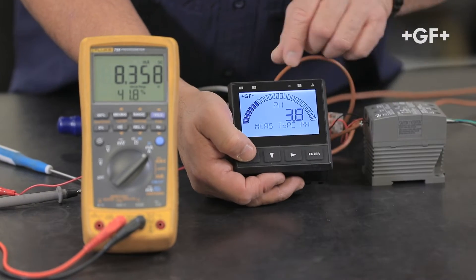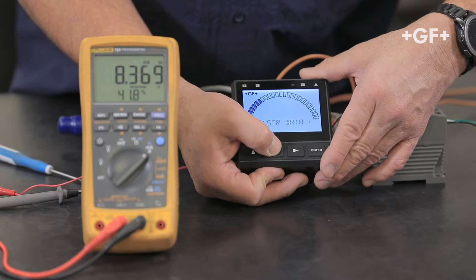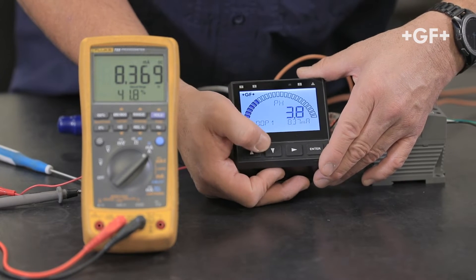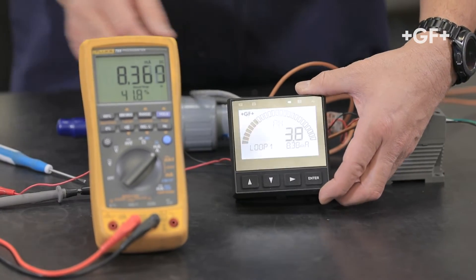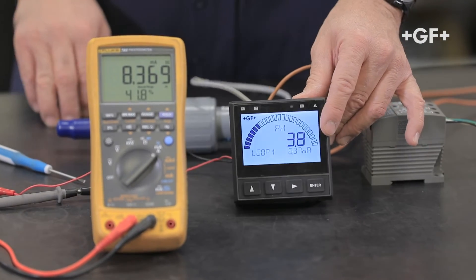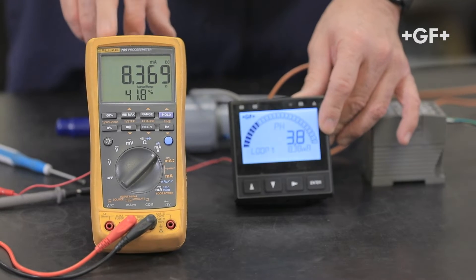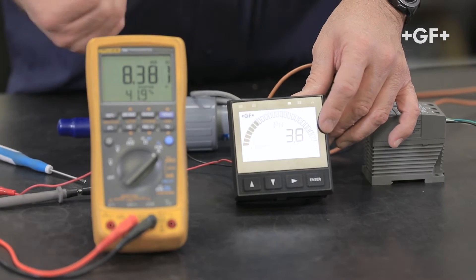Okay, so right now we're showing 3.8 pH and our output, our loop one output, is 8.37 milliamps, and that should be showing here on the screen. So if this was a PLC we would scale the PLC the same. This would be 4 milliamps at zero and 20 milliamps at 14 pH and then we would see a pH value there.